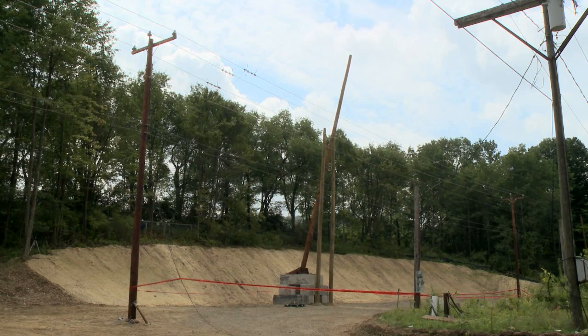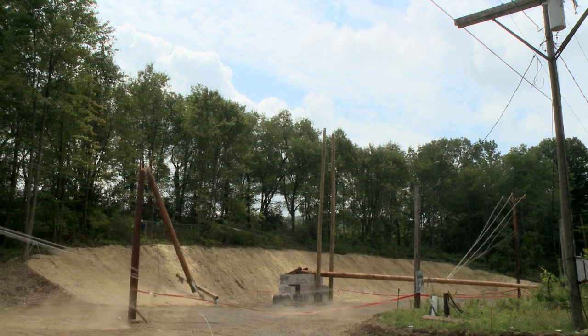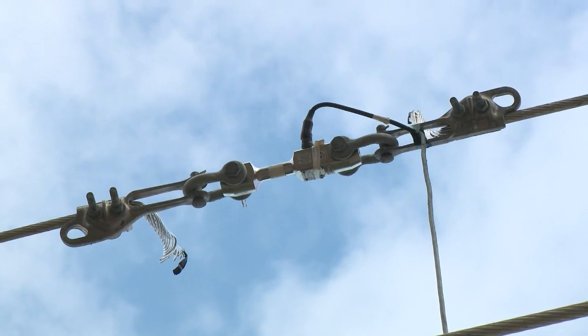The second part is how we respond and get the system back up after it's been out. So we're doing some tests — what I'll call non-typical type of impacts — where we try to mimic a tree falling into a line, for example, and look at what's breaking and how it's breaking. In each line, in each phase conductor and in the third-party attachment wire, we placed load cells that measure the amount of force that the pole and the conductors are being subjected to.